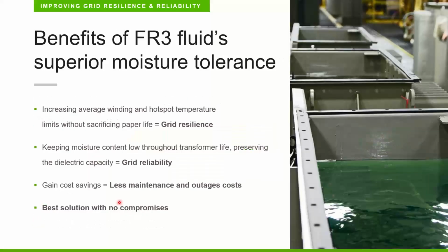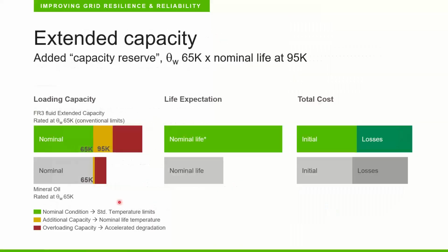Of course, this comes with a cost. Sorry, the last one, the previous one. No, just to say that this is what we can call a premium transformer. So we have a transformer that has many more options to be exploited by the utility from the operational point of view, and it comes with an initial cost a little bit higher. According to our experience, it is between 10 and 15% higher in cost. But this is true if we are comparing with the base capacity of 65 degrees. If we make a calculation with the overload capacity, the cost per MVA is lower, and then this kind of investment starts to make sense.